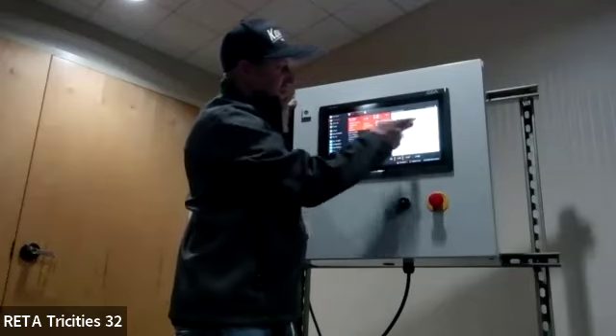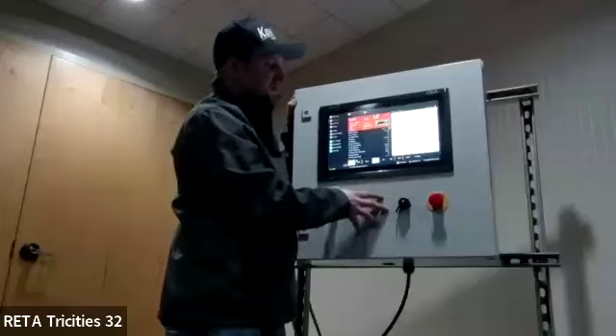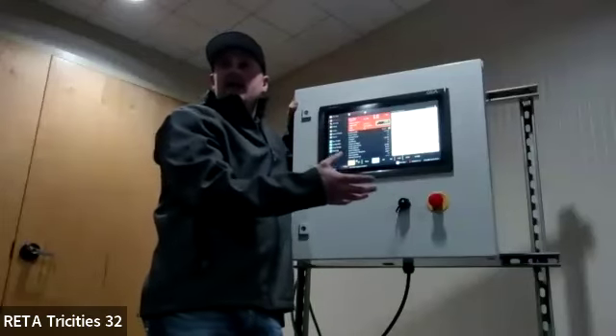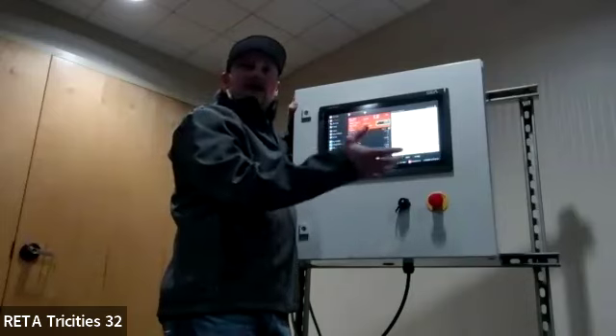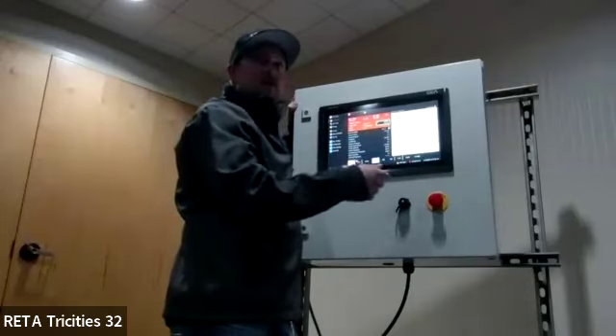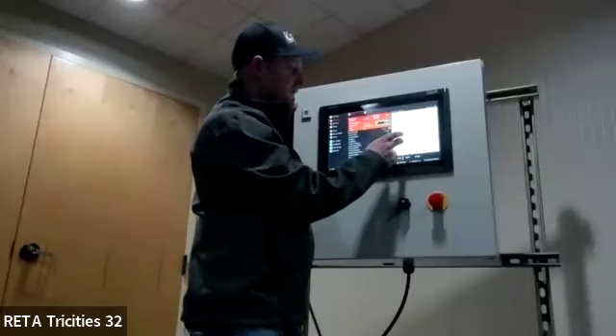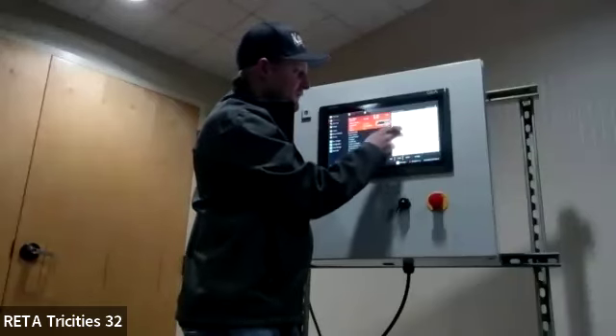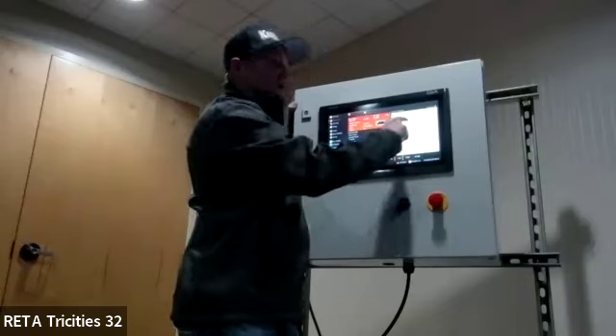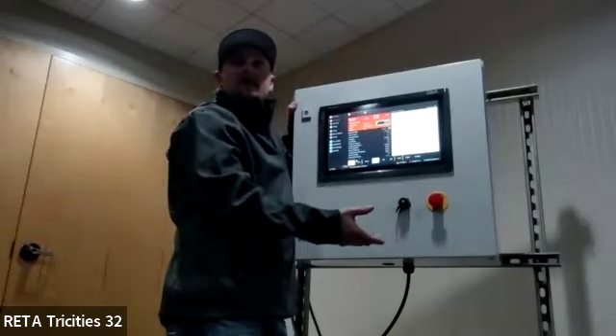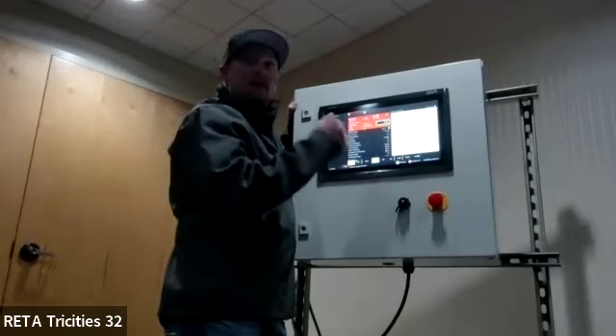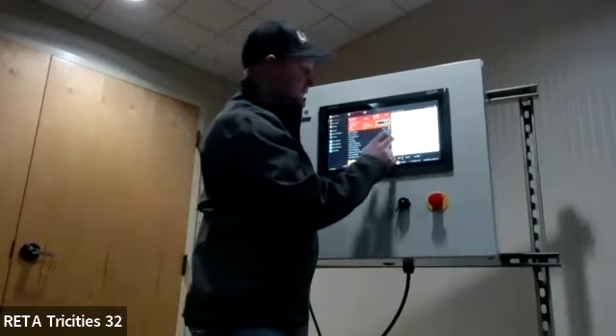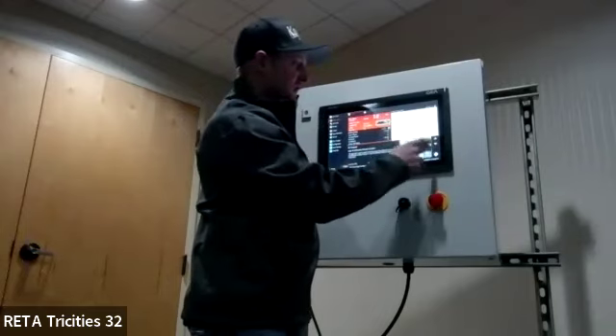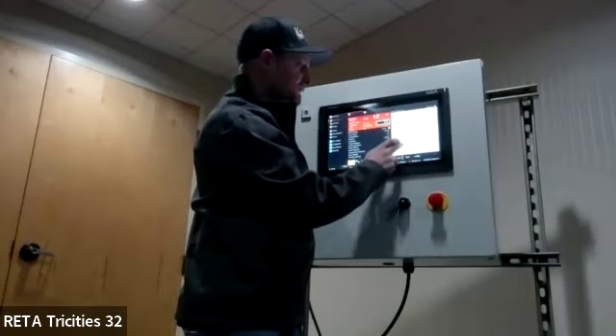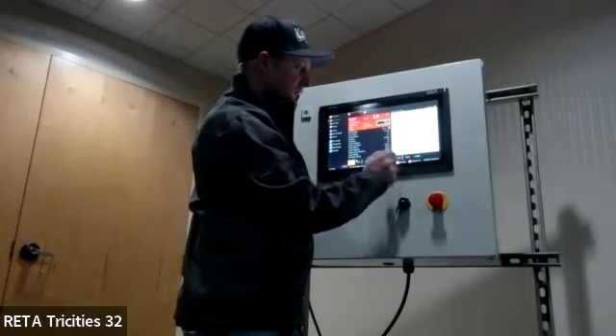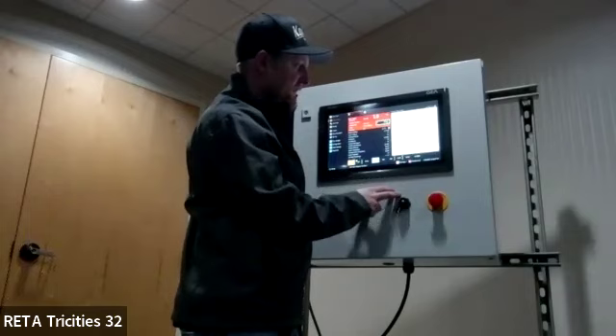Here's where you adjust motor current. So, when you set this panel up, you need to go take the motor nameplate data and do your service factors, get your FLAs and horsepowers, shutdowns, things like that. That's motor speed. Oil pump, it actually shows your oil pump runtime also. So if you put a new oil pump in, you can reset the runtime on that. You can adjust pre-loop timers. Oil pump run minimum timer, maintain timer.